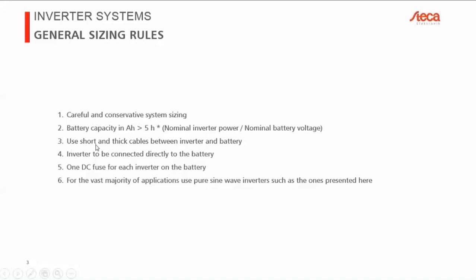Then use short and thick cables between the inverter and the battery. Typically, for off-grid inverters, very high currents are flowing between the battery and the inverter. And to ensure that we don't have too much voltage drop and that the system is running stably, we need to ensure that we have a certain minimum connection cable size, and that we also try to keep the distance between the inverter and the battery as small as possible and keep the cables as short as possible.